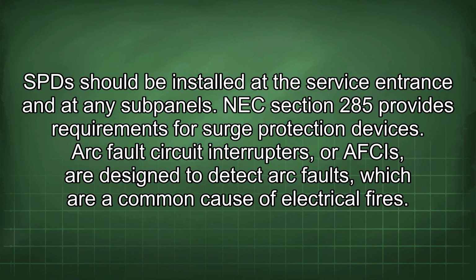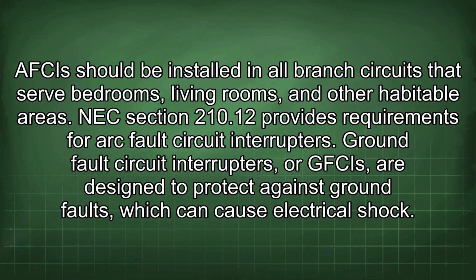Arc fault circuit interrupters, or AFCIs, are designed to detect arc faults, which are a common cause of electrical fires. AFCIs should be installed in all branch circuits that serve bedrooms, living rooms, and other habitable areas. NEC section 210.12 provides requirements for arc fault circuit interrupters.